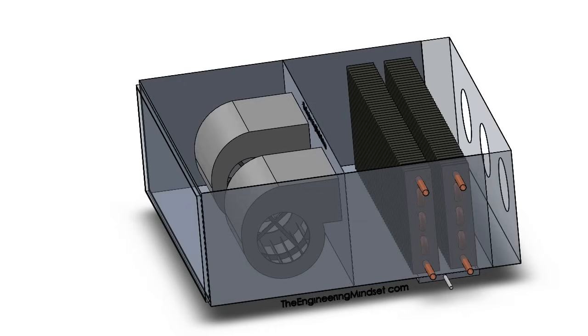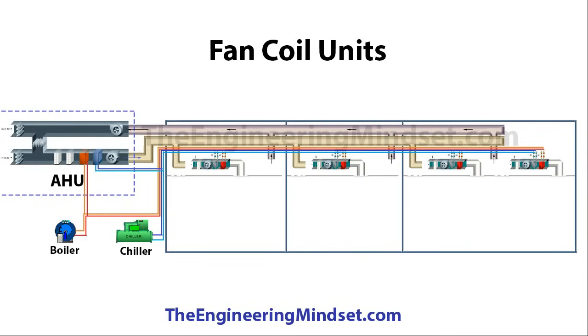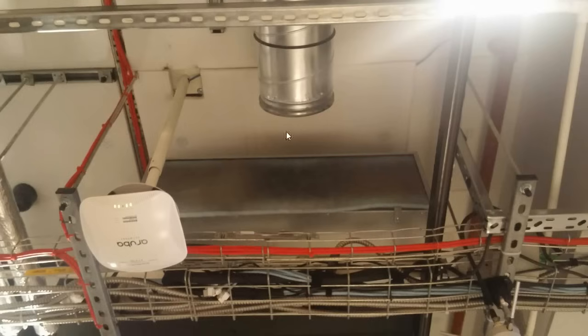Looking at this schematic of how fan coil units work: the main AHU is supplying air down through ducts to each of the rooms. Not all fan coil units will have a fresh air duct connected to them, as you can see with this one. However, each room will have a fresh air connection because there is a requirement for each room to receive a certain amount of fresh air per hour. In this example, fresh air comes through this duct to the inlet of the fan coil unit — it's not directly connected — and that air is blown in. The filter here can just be removed, pulled off or slid out, and cleaned or replaced.